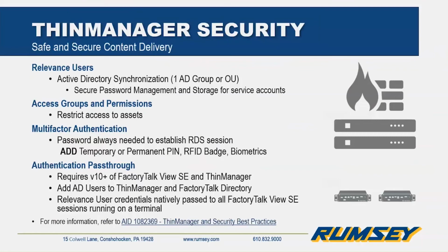We already did the pass-through. I think you saw that when we did the demo. Mark's logged into SE. That does require FactoryTalk View SE 10 or higher, ThinManager version 10 or higher, and you need to have users that are linked to an Active Directory, both within ThinManager and the FactoryTalk environment.